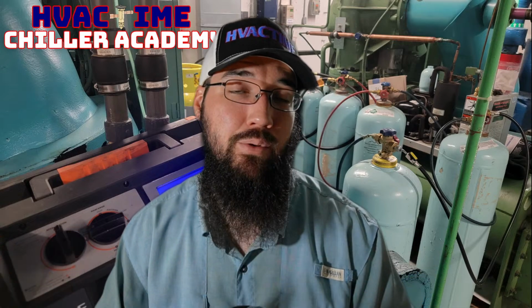And just to clarify, discharge superheat is your discharge temperature minus your condenser saturation temperature. The difference between those is your discharge superheat coming off of your centrifugal. That is the primary way that we will judge a centrifugal's superheat performance. We won't base it off of suction superheat most of the time. There are some exceptions, but most of the time we're going to base it off of the discharge superheat specifically. Most machines will run 15 to 25, 30 degrees of discharge superheat, depending on the load conditions. Some of them will get as low as 10 degrees and it's still considered perfectly normal.